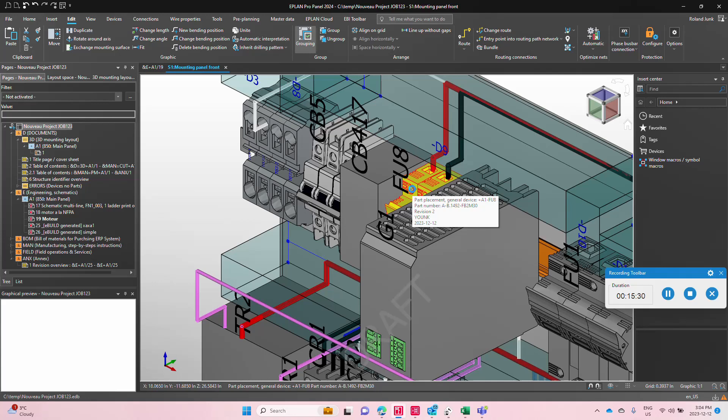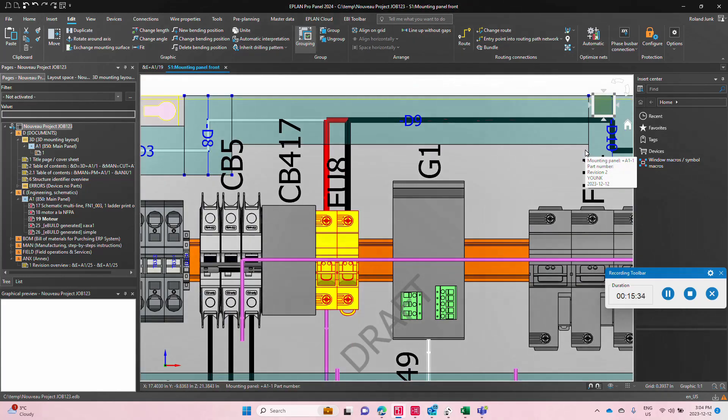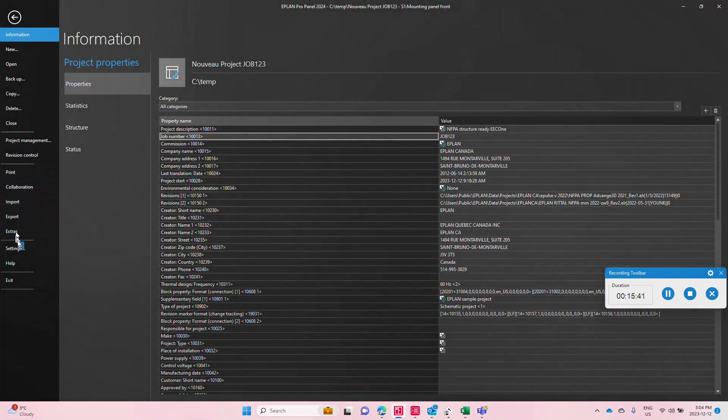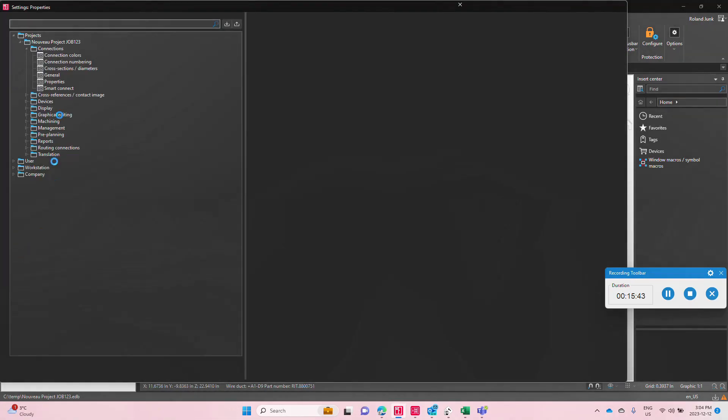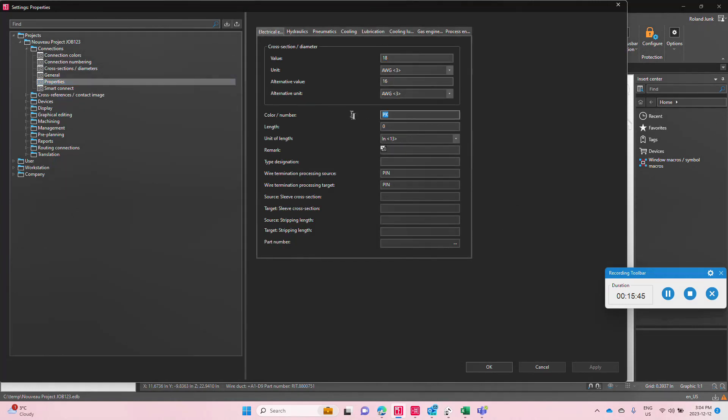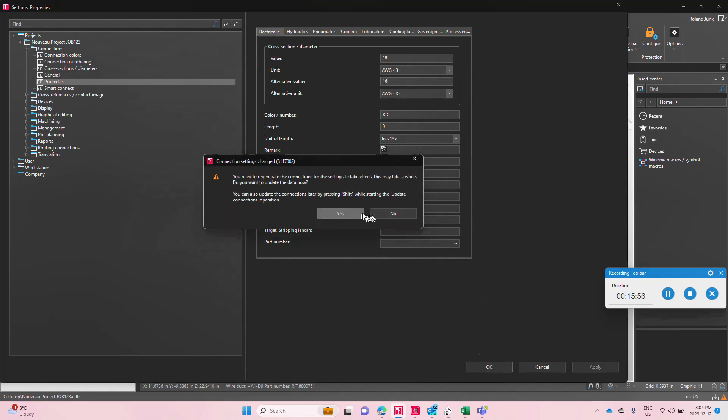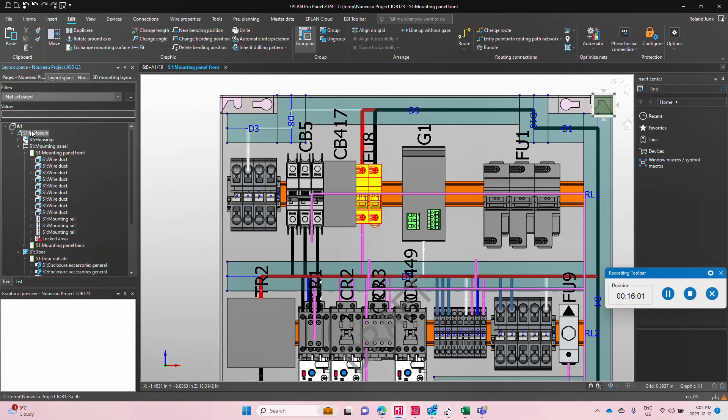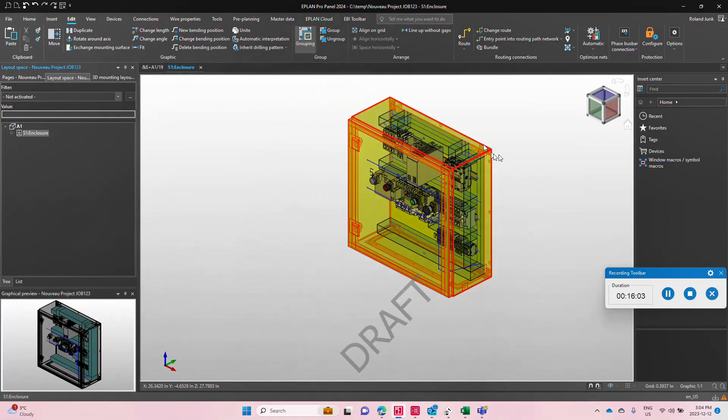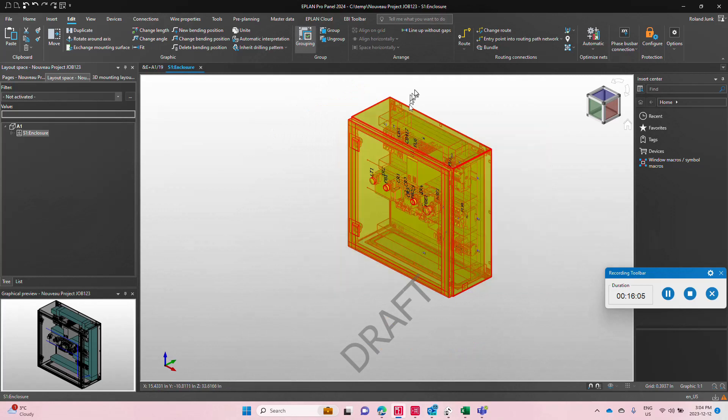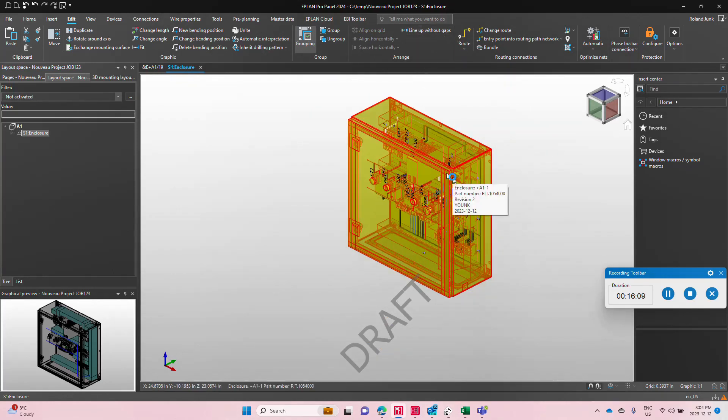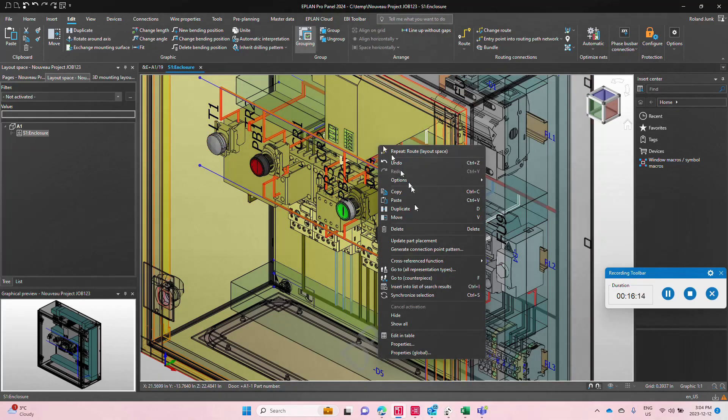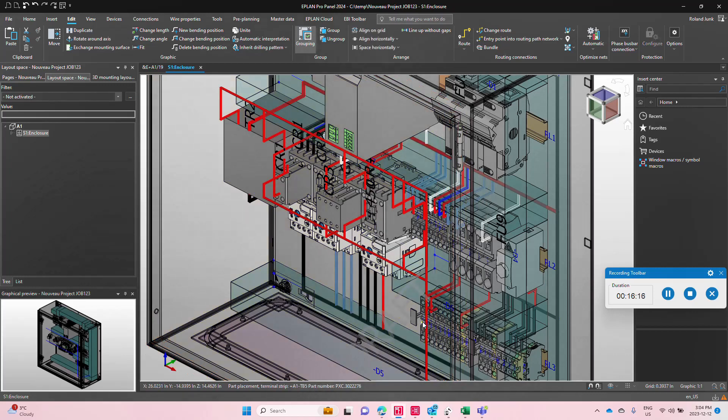So you got the idea. So once you have and you are satisfied with your routing here, you can, of course, say, OK, the wires, even though they have not been assigned with the proper color in the schematics, we actually know that my default color will be, let's say, red, a certain gauge. In this case, American wire gauge 16 or 18, whatever. And then, of course, if you rerun the routing, this will immediately run through the whole panel, and just reconsider the wires as you just mentioned. Those pink wires are then gone. As you can see here, no pink wires anymore. Even if I take out here, hide the door, you can see everything is actually colored now exactly the way I want. And we have now the exact length for each of these wires.